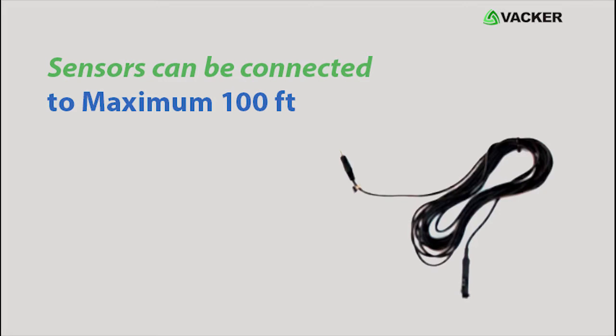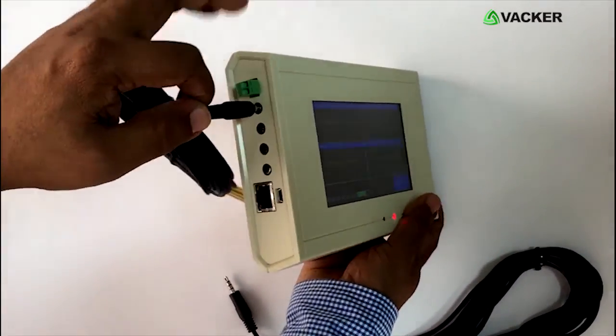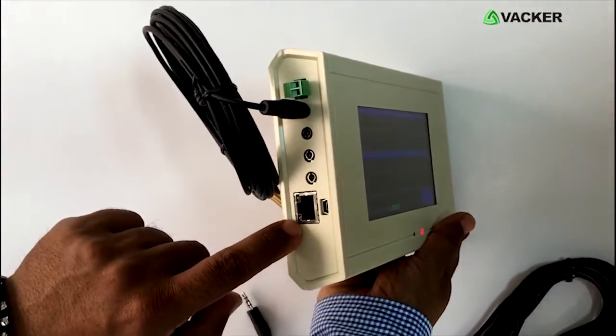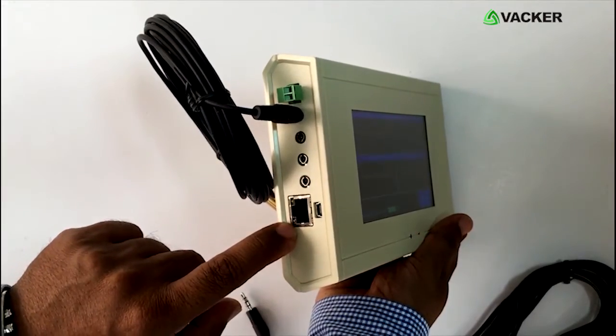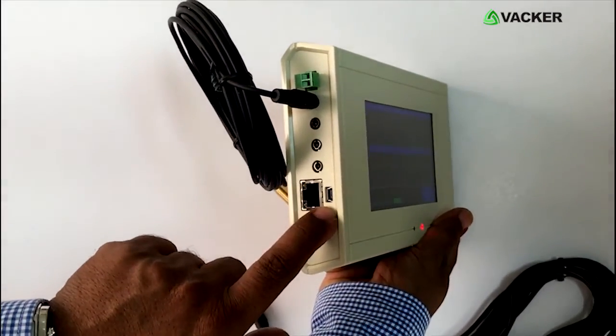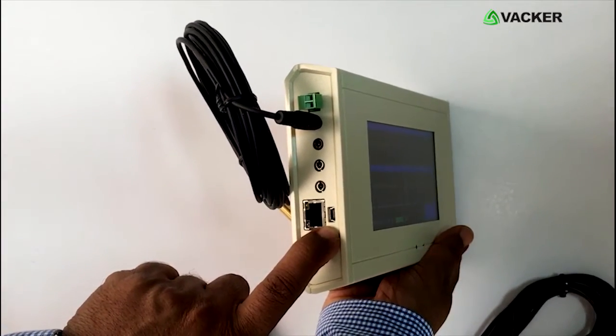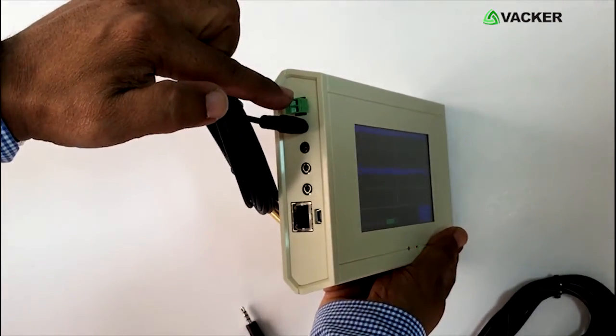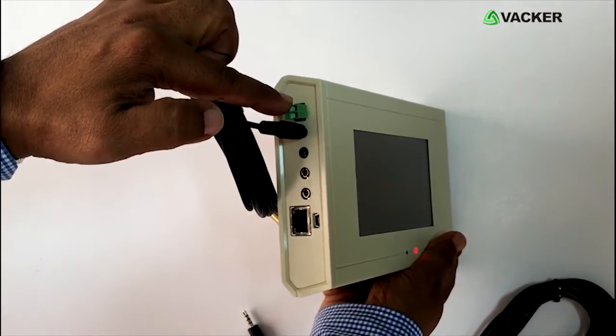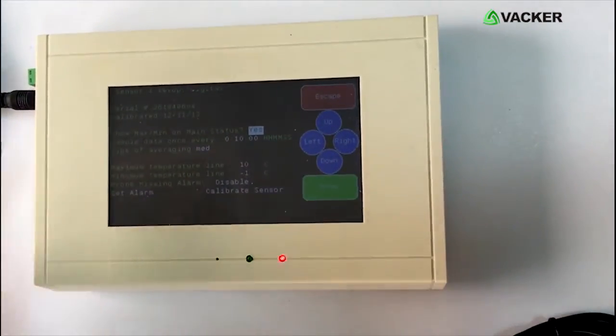We can connect sensors up to a maximum of 100 feet. The first sensor is now connected. You can see there are four ports — this port is for connecting to a network, these are for four sensors, and this is for downloading the data by USB as well as for charging. This contact is for generating phone call alerts. You can see that sensor 1 is automatically detected.